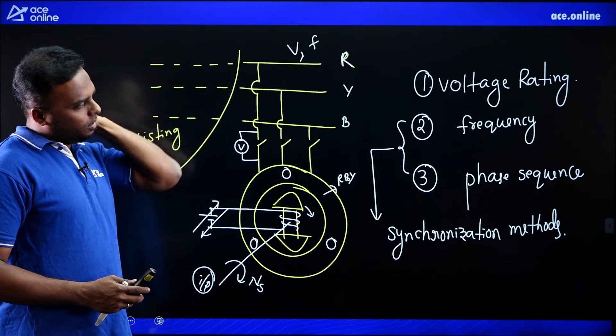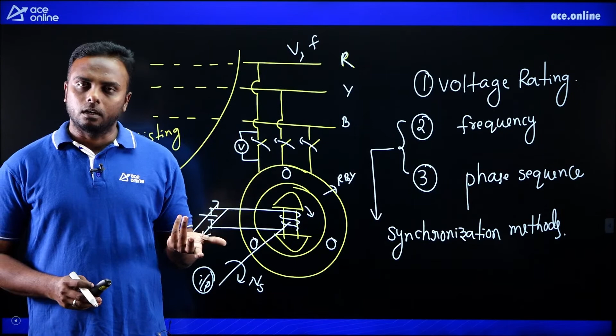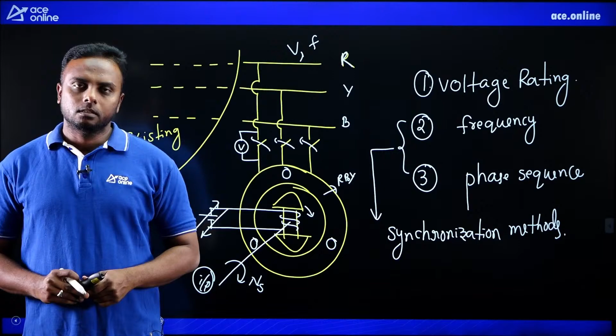Okay, so these are the three conditions we need to verify before connecting this alternator to the bus bar. Suppose all the conditions are verified and satisfied, such that the bus bar and alternator have the same values, then close these switches. Now the alternator is connected to the bus bar, and it will operate, just as the other alternators already operating in parallel do. Okay, now let's see the synchronization methods: how to synchronize and what methods we use for this.